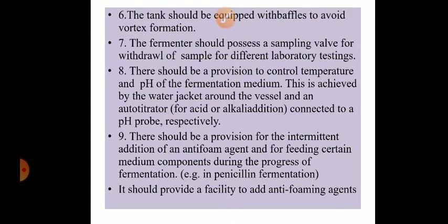The tank should be equipped with baffles. Okay, baffle walls should be provided inside the vessel to avoid vortex formation, to break the bubbles that form during agitation or during rapid mixing of the medium. The bubbles that develop, the vortex that develops should be broken. That is why we need baffle walls from the inside of the tank.